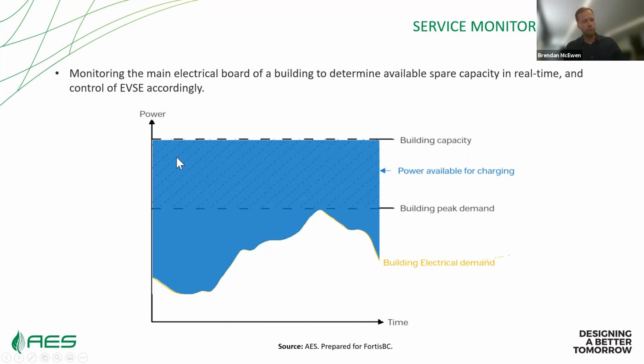This allows you to design buildings, according to the electrical code, to exceed and have more EV demand, avoiding things like a service upgrade or transformer upgrade that would otherwise cost developers a fair bit of money. Instead, they can plan to implement service monitoring if they're approaching the building's capacity, taking advantage of the space underneath that peak line.